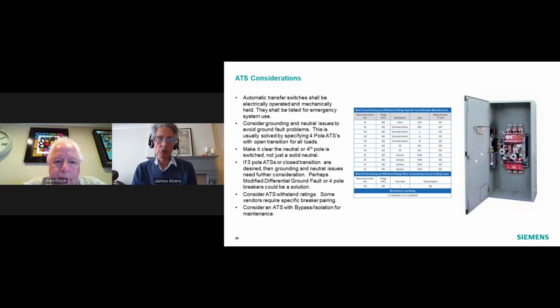So I know we're primarily talking about switchboards, but ATSs are a huge consideration for these switchboards. The code requires that they be electrically operated and mechanically held for emergency applications. And they're listed for system use. What that usually means is you need a UL 1008 ATS. It's very important to consider grounding and your neutrals for generator switchboards. Usually this is solved if you use 4-pole ATSs. So if you specify 4-pole ATSs and you want to make sure the fourth pole is not just a solid neutral, but an actual switching pole, you can avoid a lot of the issues with grounding and neutrals.